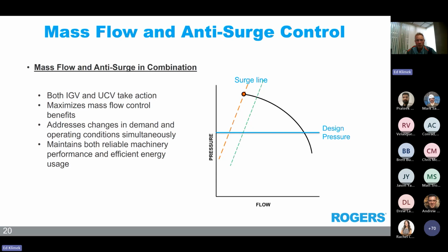So here's an example. Let's look at a scenario in which the compressor is running in the winter, which also happens to be a slower time for plant operation. Let's say this is during the holiday season. Since the ambient temperature is colder than the normal operating conditions, you have less volumetric flow. So you have less flow, which is required to obtain the designed mass flow. Thus the current IGV setting exceeds the mass flow design. At the same time, there is less air usage downstream of the compressors since operations have slowed down. I'm going to try to animate that situation.